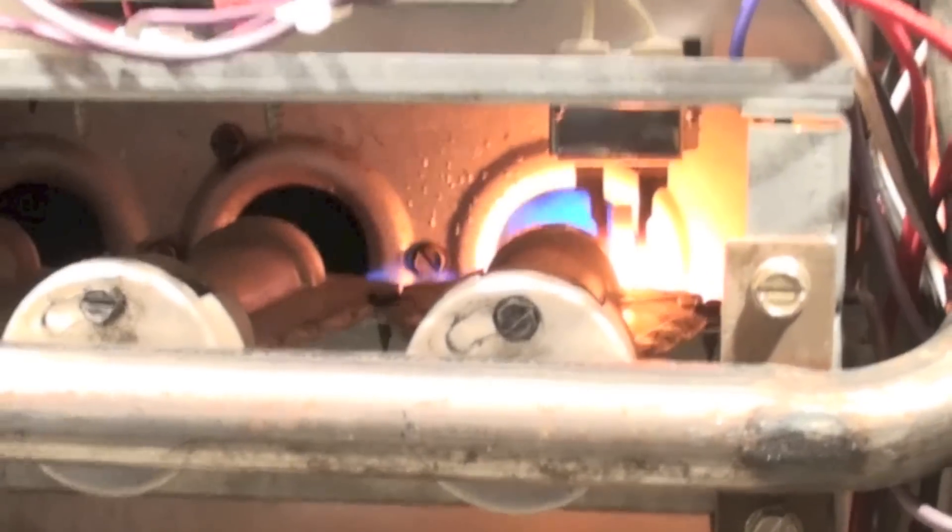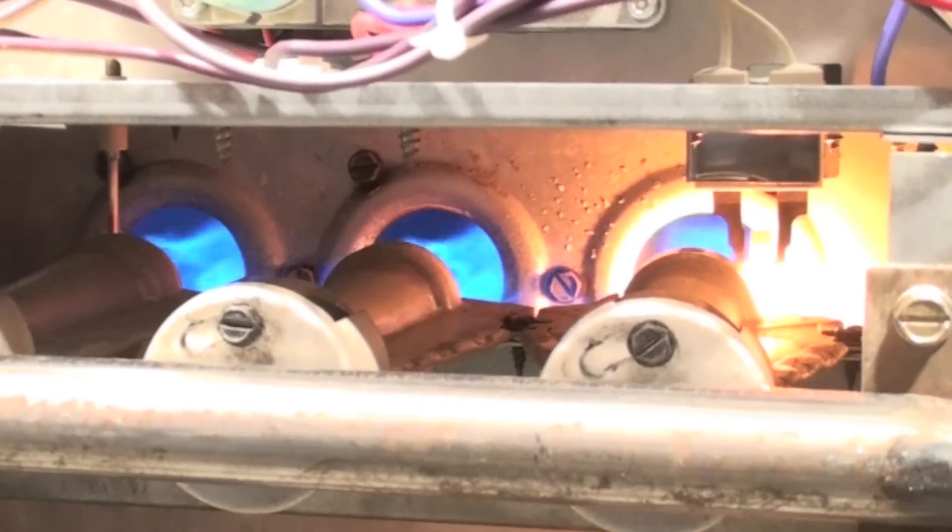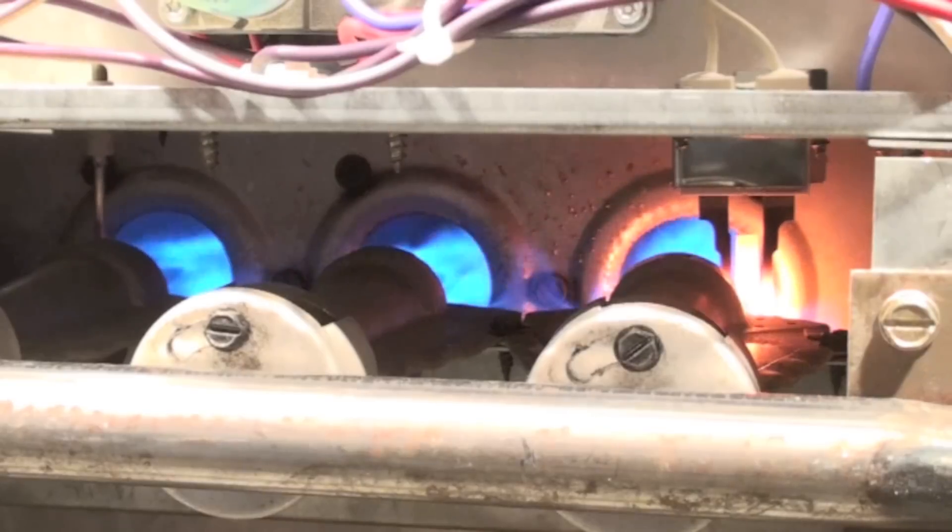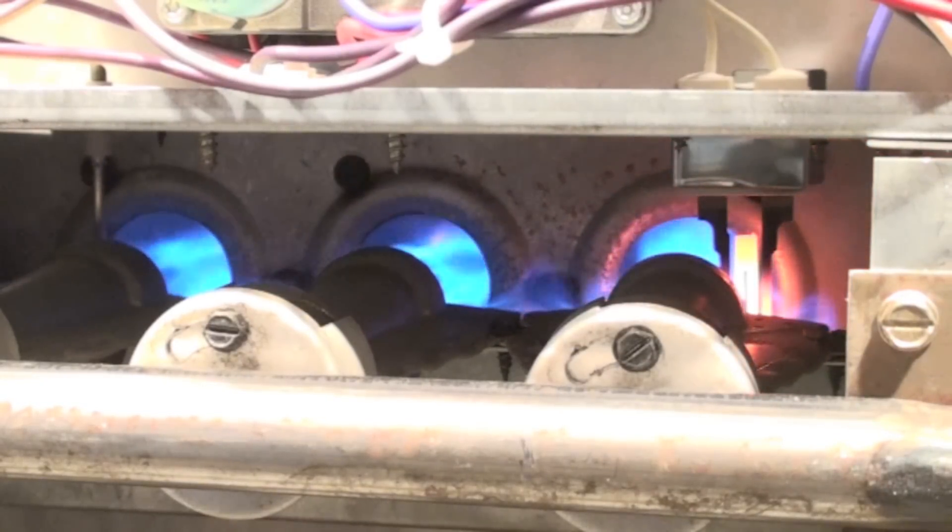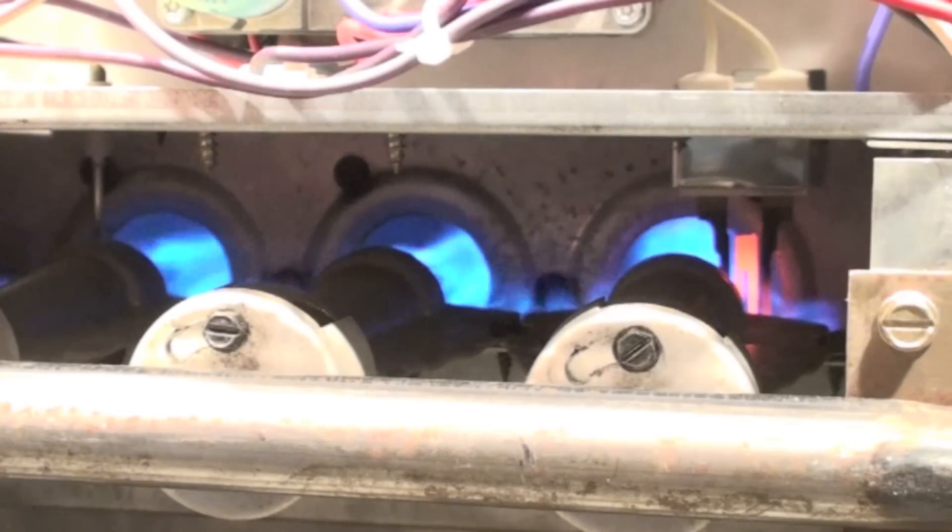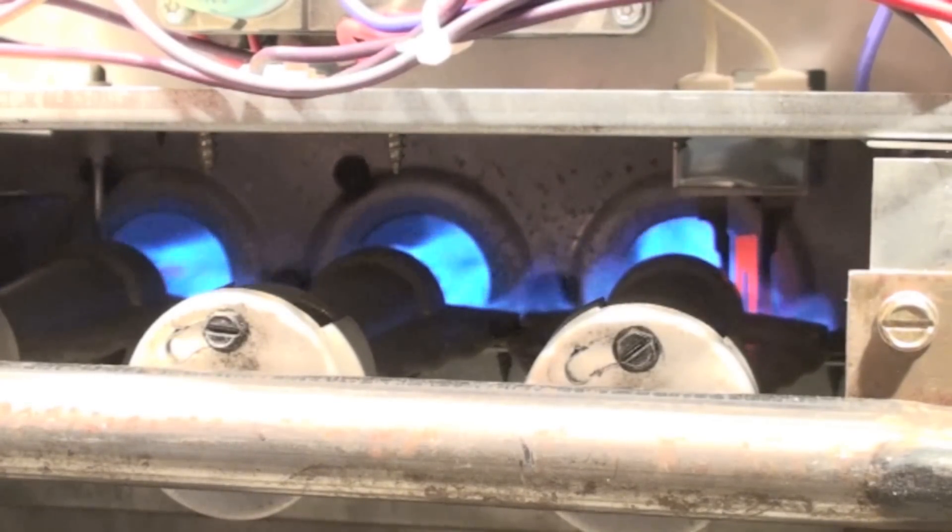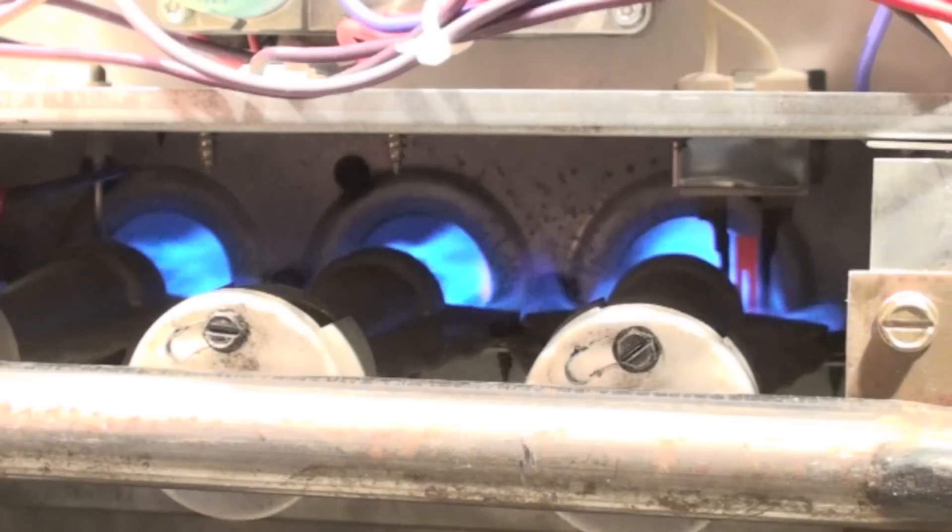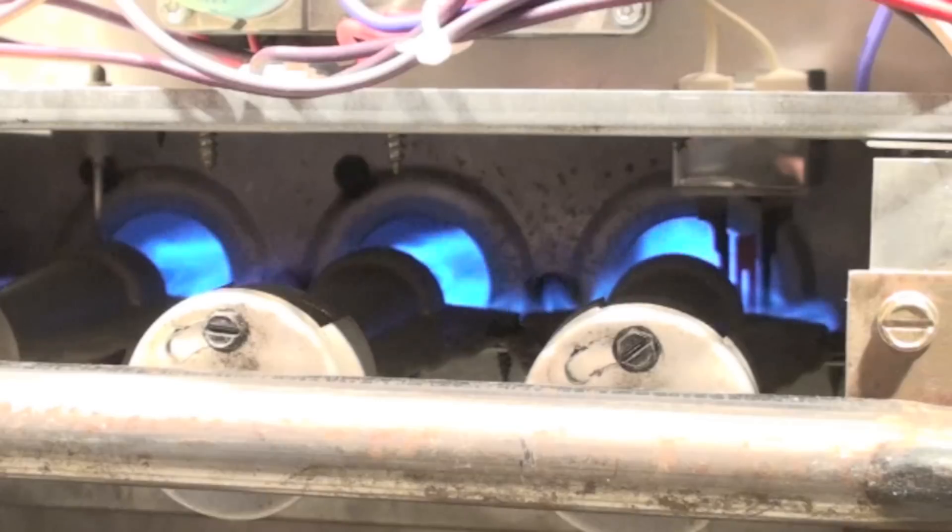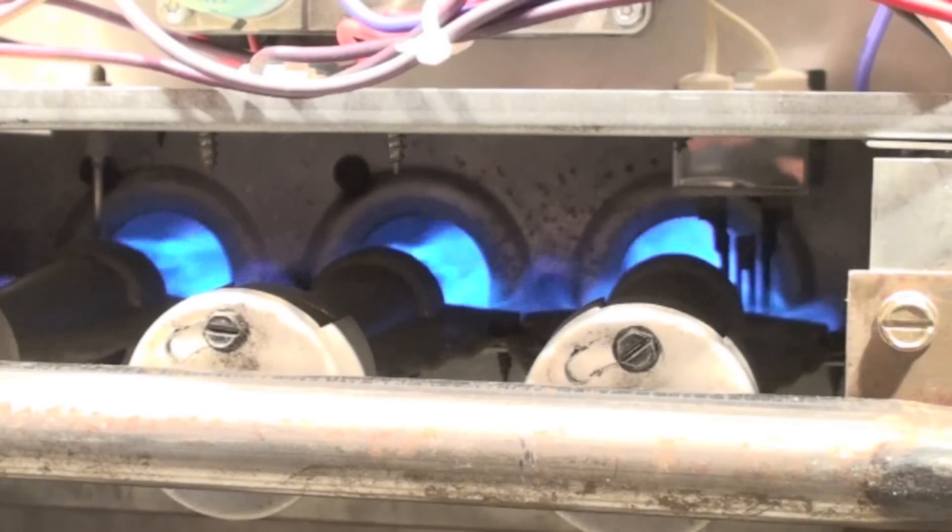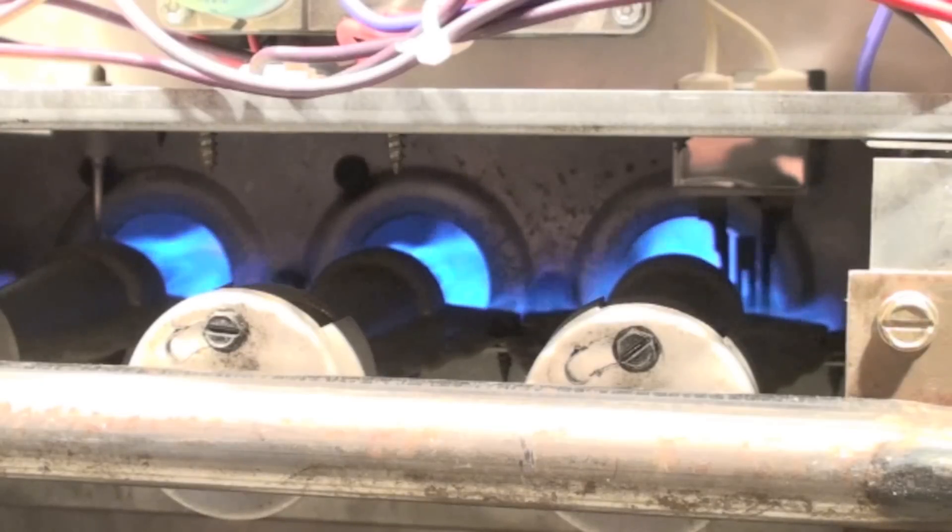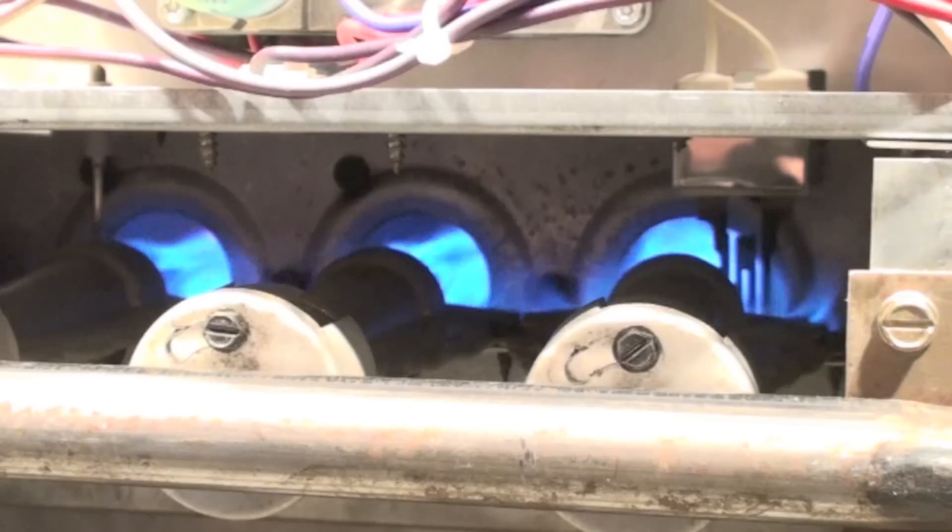It's going to give the burners a chance to light. Right over there on the left side is a flame rod—that doohickey right back there, a little hard to see, but it's in the flame. It sends an electronic signal back to the IFC telling it that the flame is established. Once that flame's established, it's going to start a timer for the indoor blower. Here the indoor blower comes on.